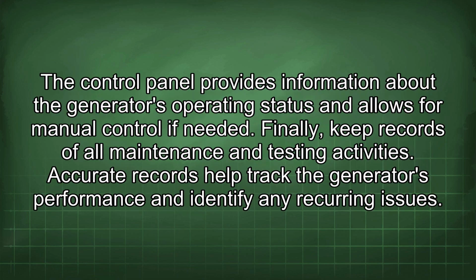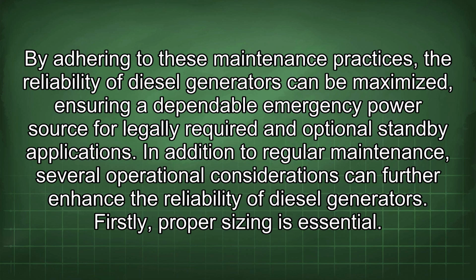The control panel provides information about the generator's operating status and allows for manual control if needed. Finally, keep records of all maintenance and testing activities. Accurate records help track the generator's performance and identify any recurring issues. By adhering to these maintenance practices, the reliability of diesel generators can be maximized, ensuring a dependable emergency power source for legally required and optional standby applications.